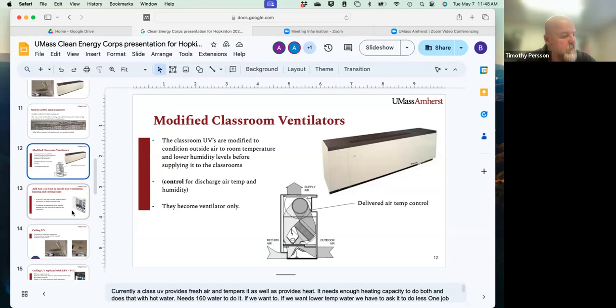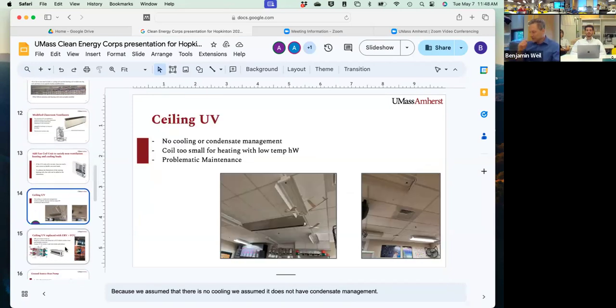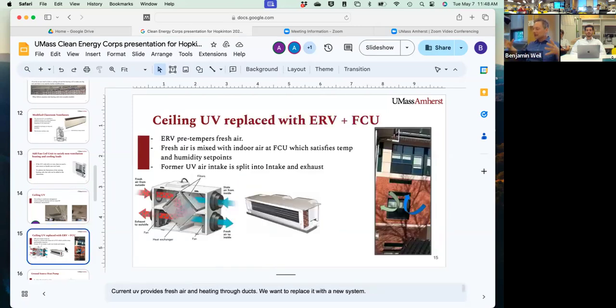The difference is with the ceiling unit ventilators, which you identified as being problematic. If they don't have any condensate management, even if they do have an extra coil just sitting there, we still can't do cooling with them. If you want to do cooling, it might be simpler just to replace them. So if you're going to replace them, then we can integrate a new system. We take a residential ERV, just like for a big house, and hide it up in the plenum. It feeds the return side of this fan coil unit, which is now a fan coil unit sized for cooling and for heating at the low temperature hot water.